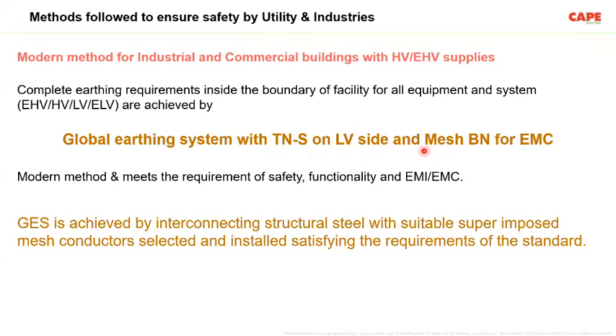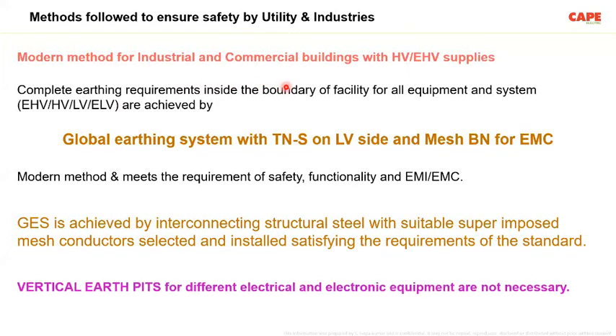Similarly, for the same system, if you go for a mesh bonding network, an MBN, for electronic apparatus, you will achieve a very high degree of safety for your electronic devices. This is the most modern method, which is recommended in the IEC standard. Of course, in this kind of system there is no earth pit and no vertical earth electrodes in the soil. Sometimes they are required, but not 200 or 500 of them, probably 3, 4, 5. But the biggest advantage of this system is that touch voltage is nearly negligible, and your devices get a very high degree of safety.